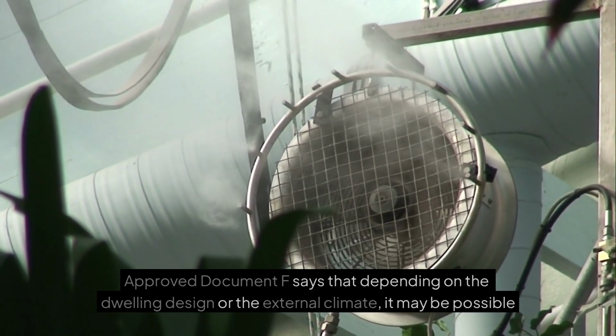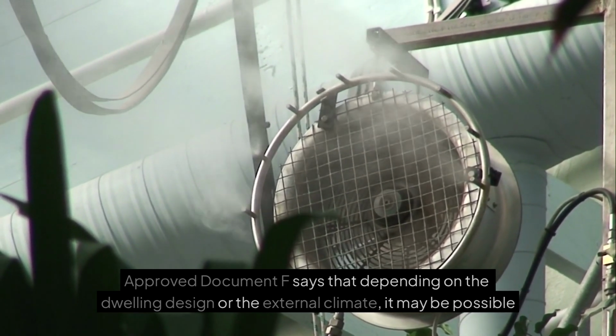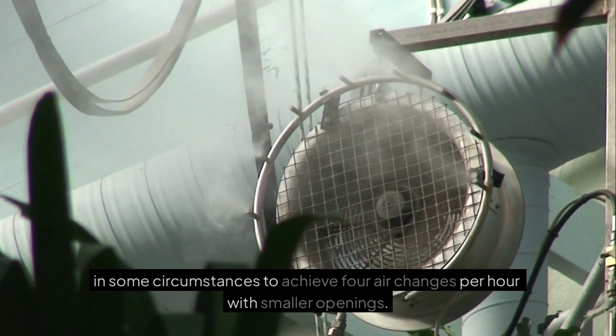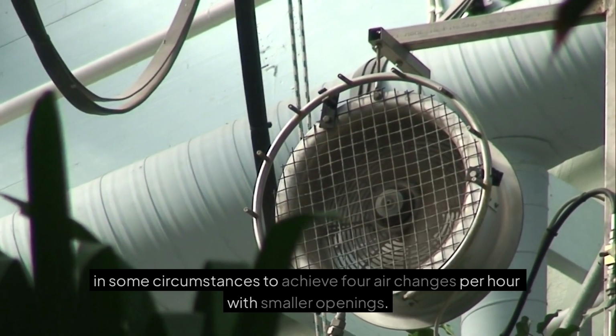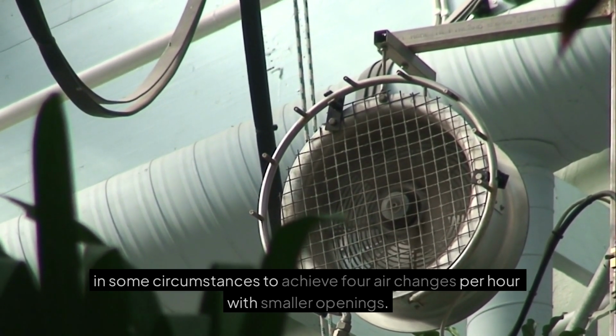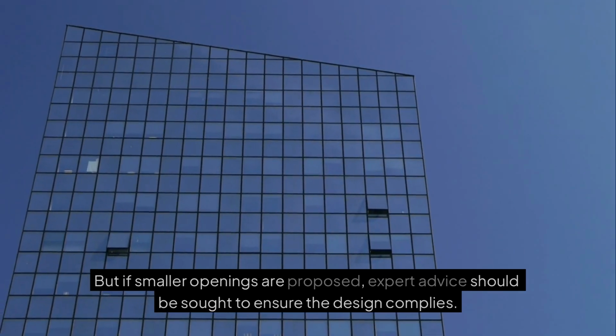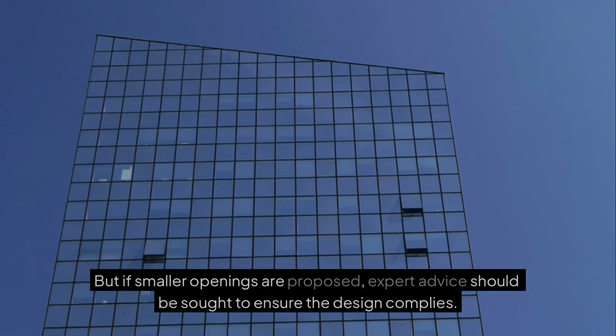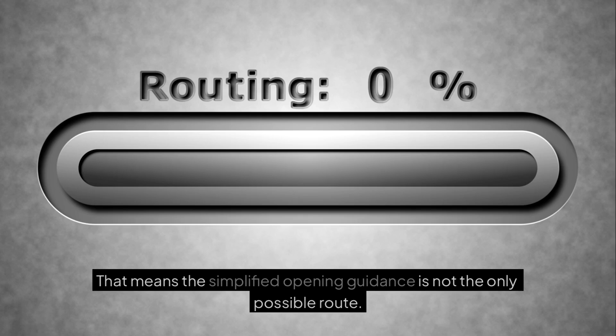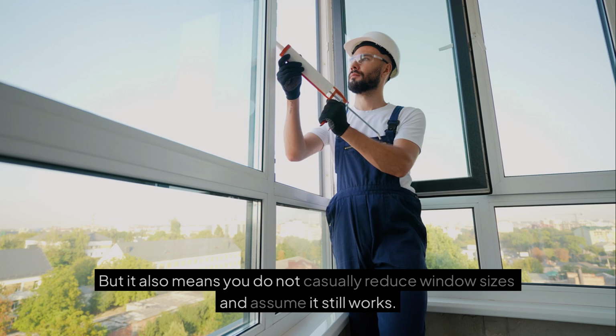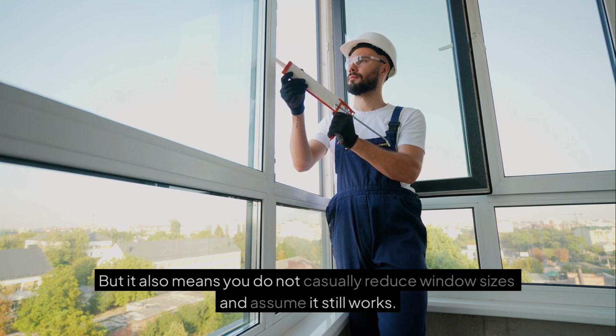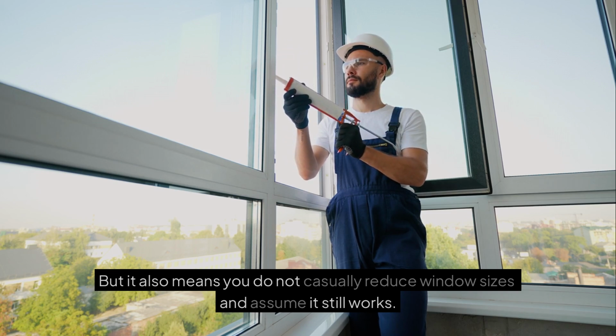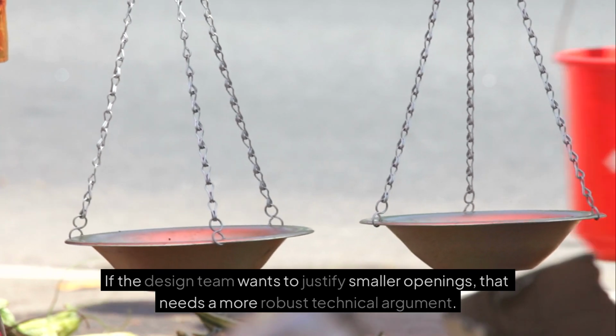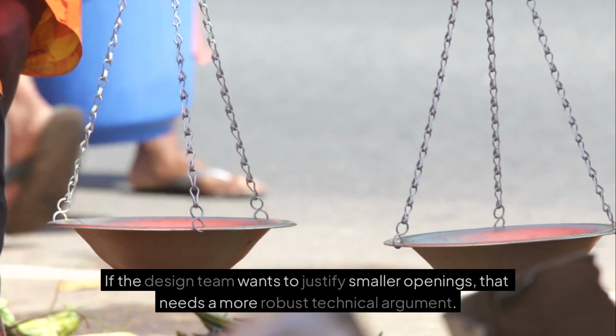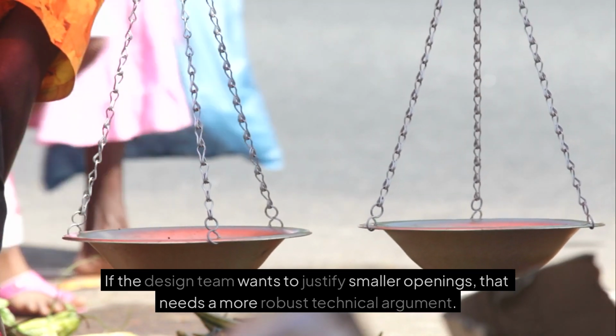Approved Document F says that depending on the dwelling design or the external climate, it may be possible in some circumstances to achieve 4 air changes per hour with smaller openings. But if smaller openings are proposed, expert advice should be sought to ensure the design complies. That means the simplified opening guidance is not the only possible route. But it also means you do not casually reduce window sizes and assume it still works. If the design team wants to justify smaller openings, that needs a more robust technical argument.